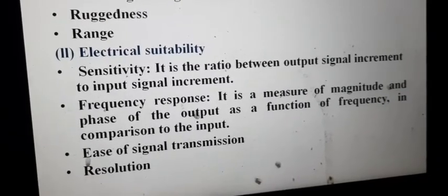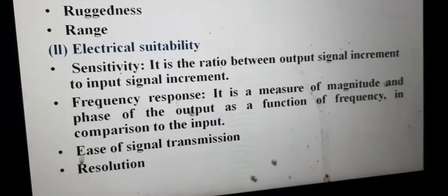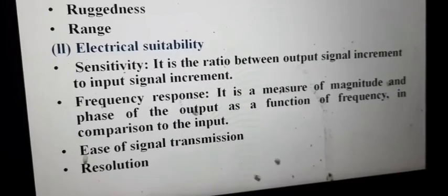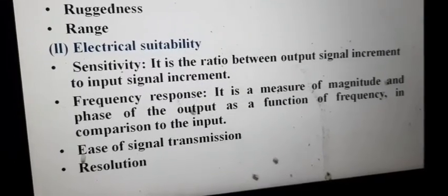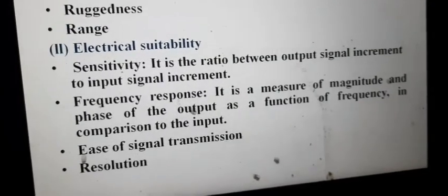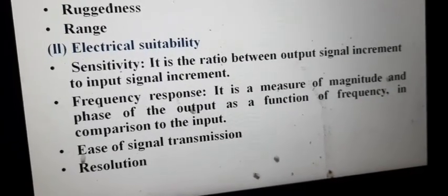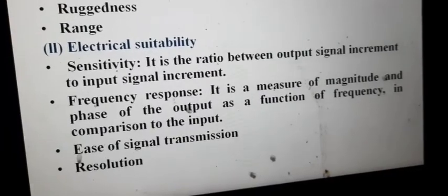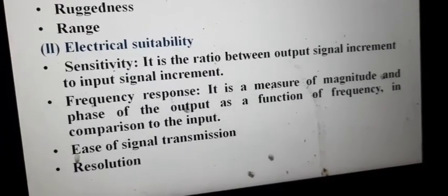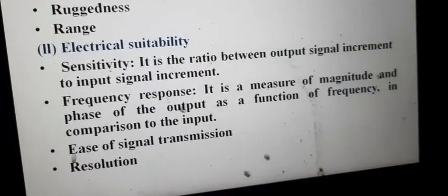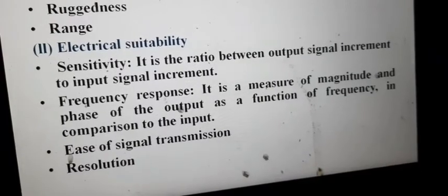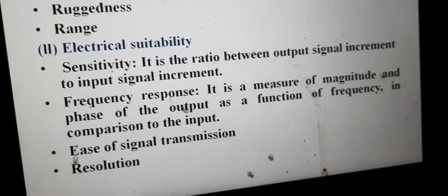When you purchase an instrument, the sensitivity value is provided by default. Your transducer should have high sensitivity. For example, in a pressure measuring instrument the sensitivity value might be given as 1.55 millivolt per pascal — whatever voltage reading you get, you divide it by the sensitivity to get the pressure value in pascals. So select a transducer with higher sensitivity.